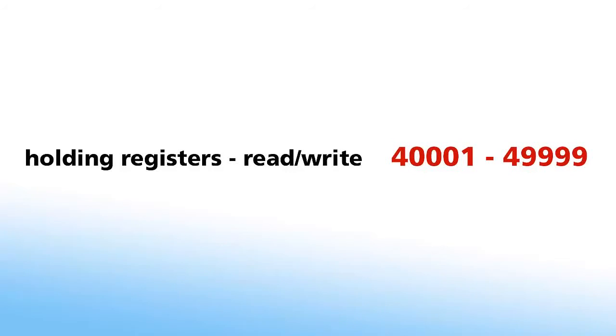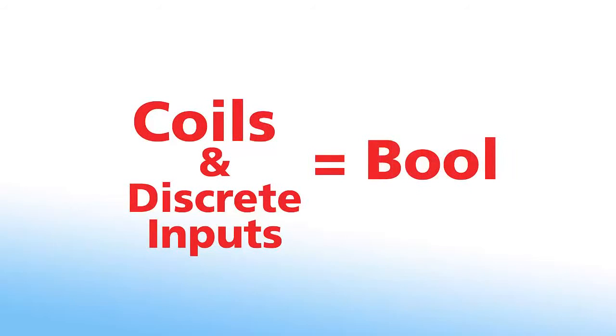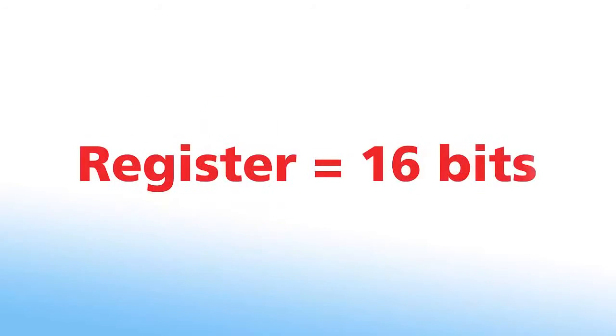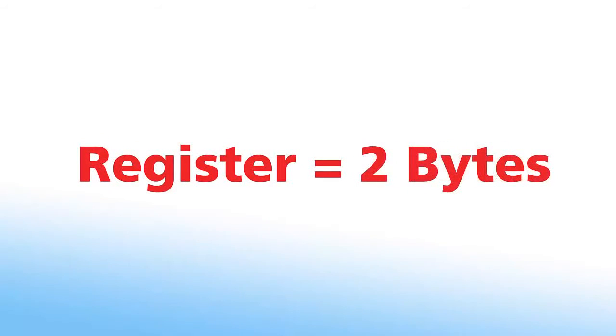At this point, it might be helpful to explain the terms used for data types in Modbus. Coils and discrete inputs are the Modbus vernacular for one bit of data or, in Rockwell terms, a bool - basically on or off. A register is the term for one word or 16 bits or two bytes of data or, in Rockwell terms, an int.